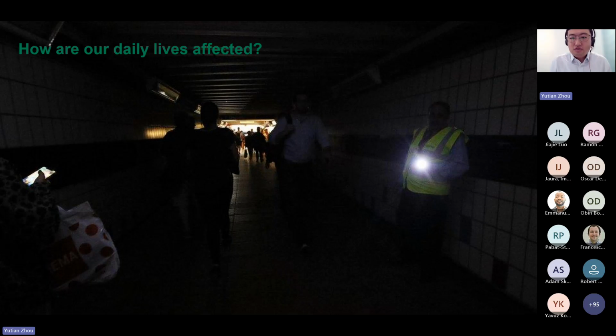So this goes back to 2019. A lightning strike occurred on a transmission circuit at about 4:52 p.m. on a Friday, 9th August. And as a serious event happened, that led to, in total, 1.1 million electricity customers being without power for between 15 and 45 minutes. And the impacts on other critical facilities, including hospitals and Newcastle Airport, were very, very significant.